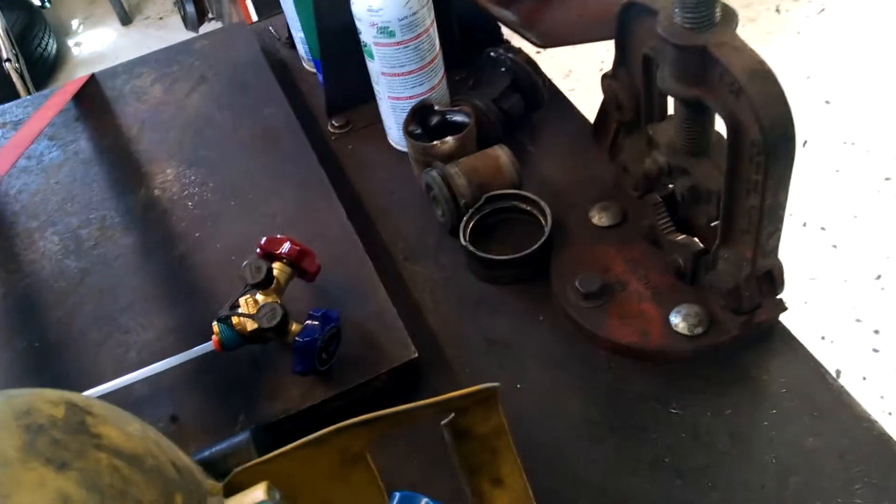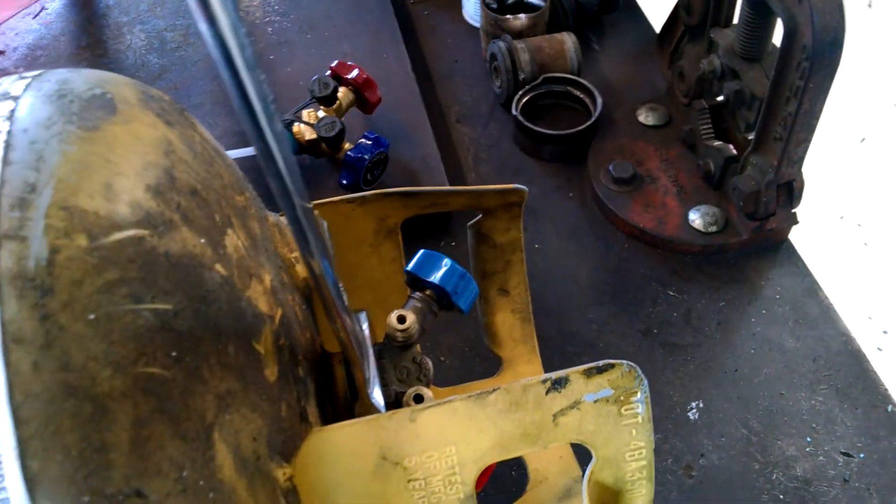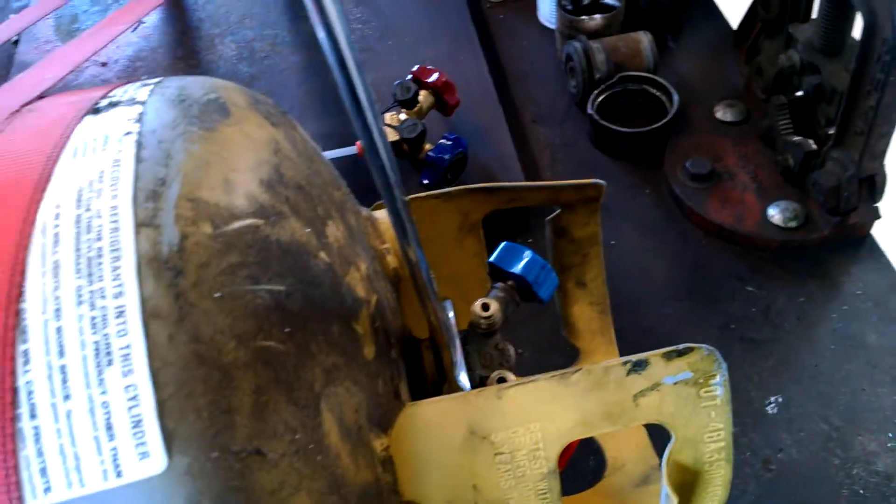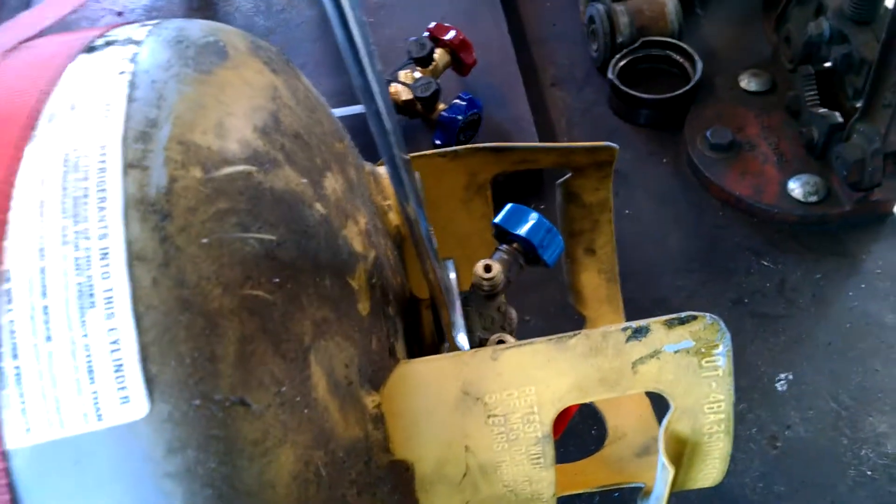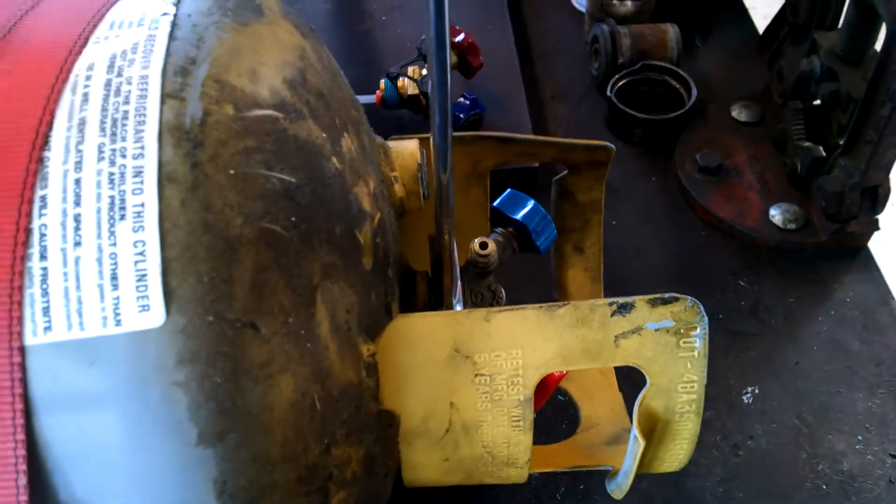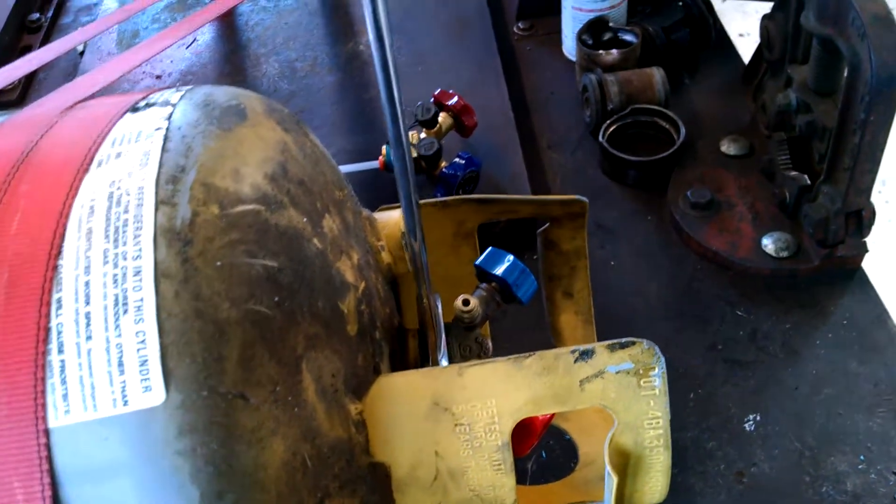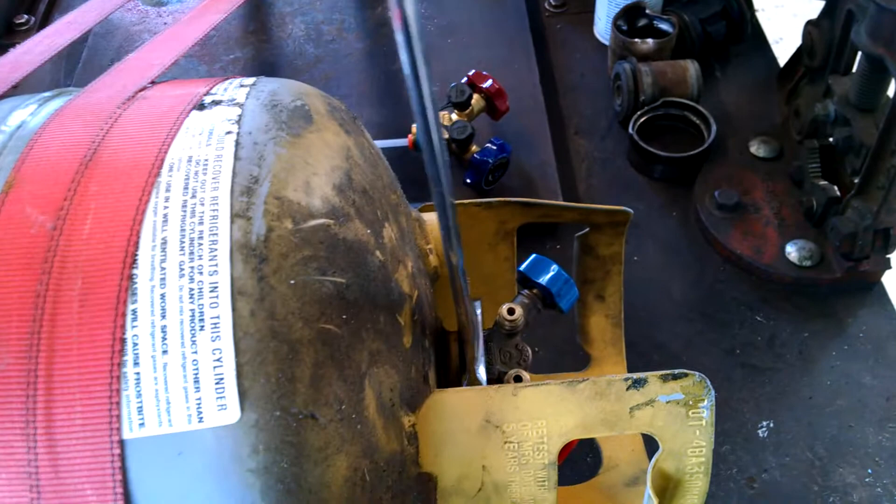We'll put a wrench up on here. This one's an inch and an eighth. Not propane, so we're not worried about non-ferrous. But if you're doing a propane tank, make sure it's emptied and pumped full of inert gas. Again, it needs to be hydrostatically tested at an appropriate facility. These are set for about every five years of retest on these Freon tanks.